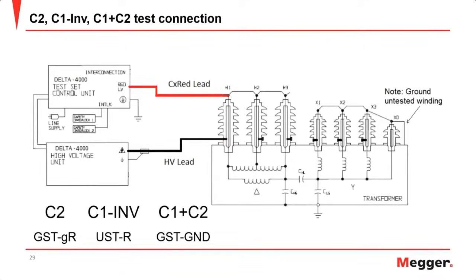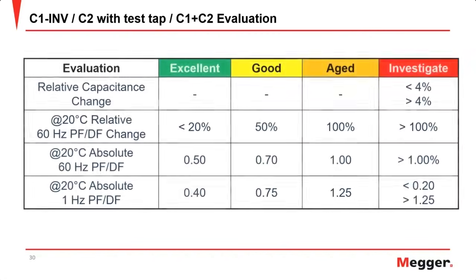Again, for the C2 test, we want to only think about those bushings that have the potential tap, where that C2 is controlled. When we have that, we can use the same evaluation that we had for C1 to also evaluate the C1 inverse, C2 with test tap, and then also the C1 plus C2 evaluation. That's what you'll see in the software: there are only a few settings for evaluating bushing C1, C2, as well as the inverted and the C1 plus C2.